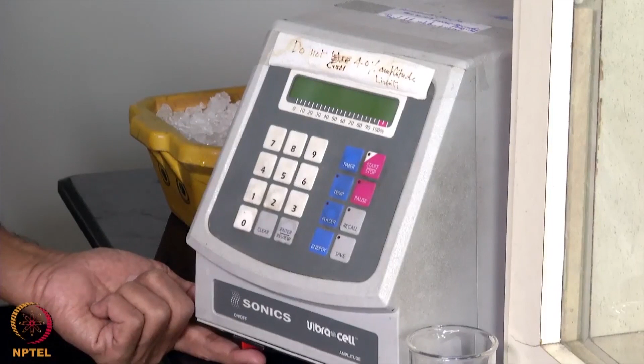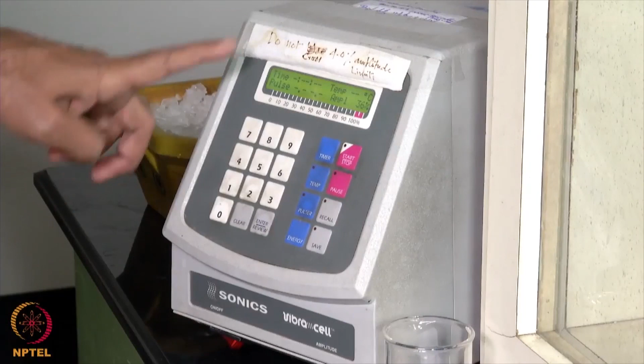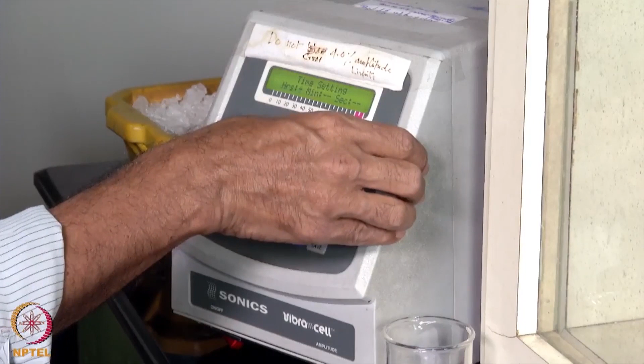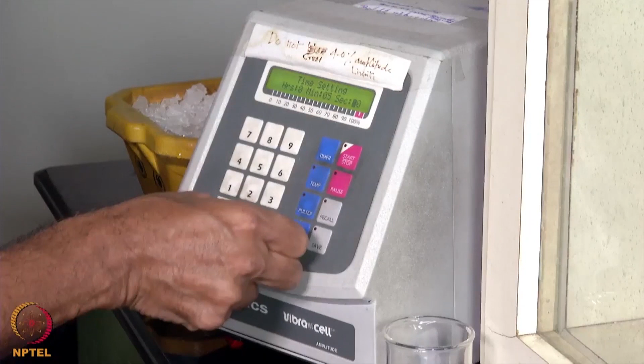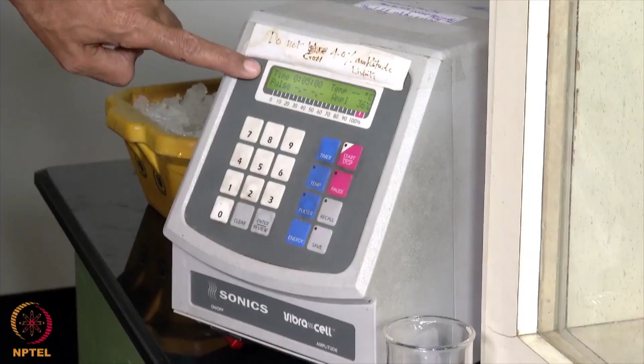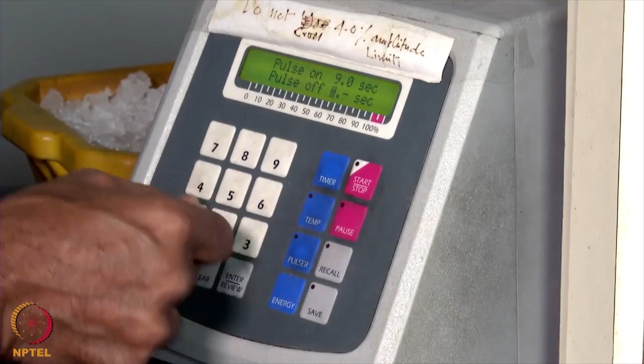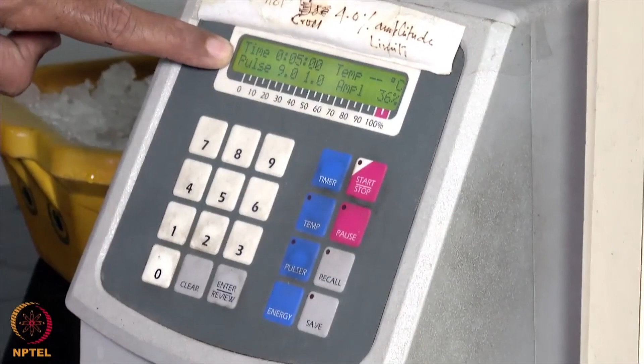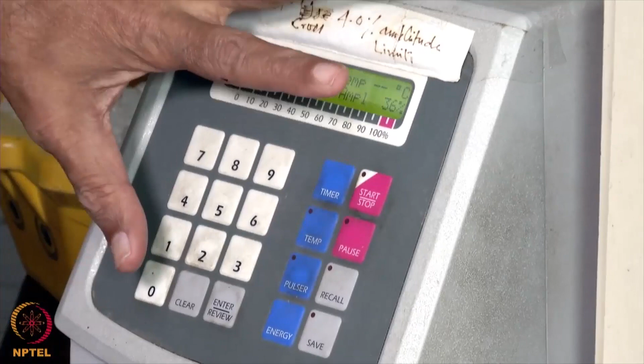We will switch on the control unit of the probe sonicator. We will set the sonication time for 5 minutes. We have set the time for 5 minutes. Now we will set the pulse. Pulse on for 9 seconds. Pulse off for 1 second. Enter. So it's got pulse on for 9 seconds, pulse off for 1 second. It's going to be done at cold temperature.